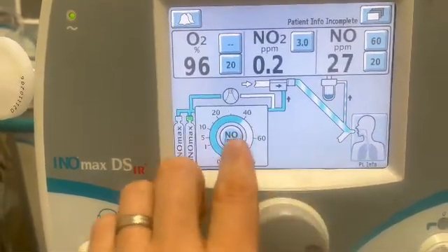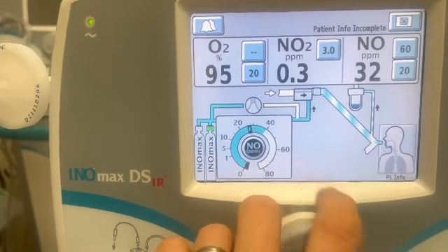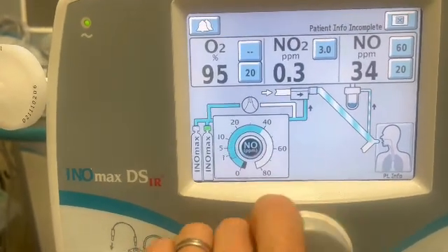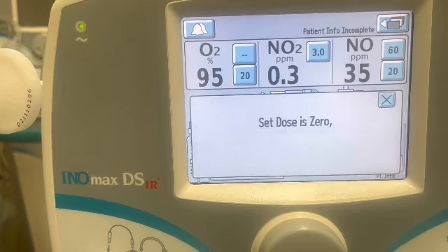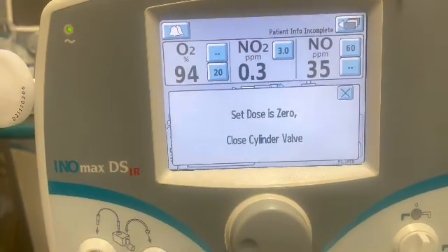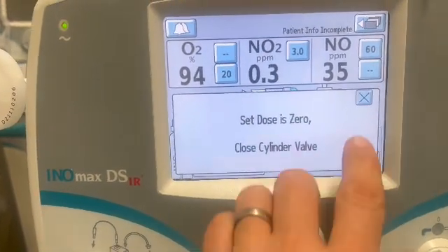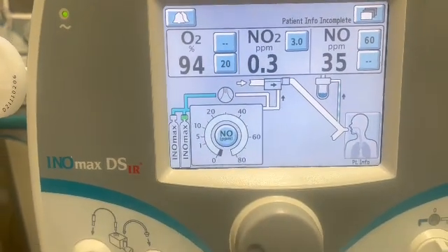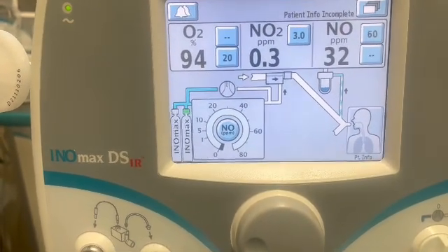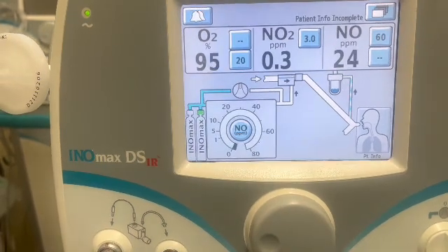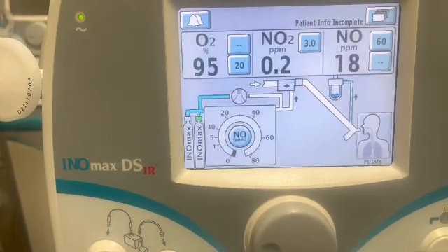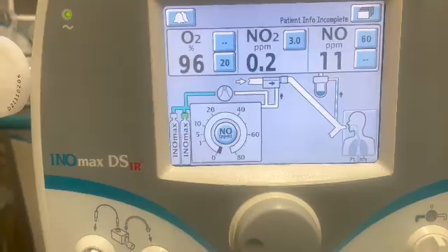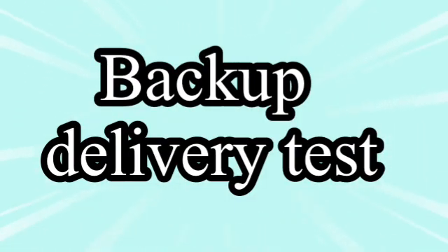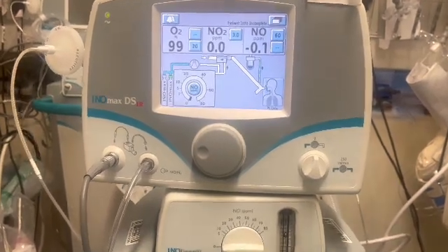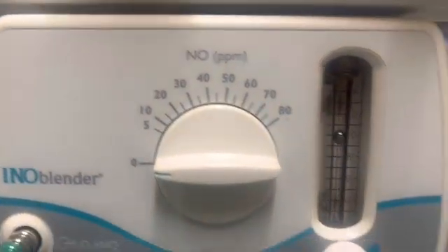Press the middle icon and turn the dial to turn the dose to 0. Set dose is 0, close cylinder valve always comes up when the set dose is 0. Don't turn the cylinder off at this time. You have left the cylinder on as you will now perform some tests on the machine.